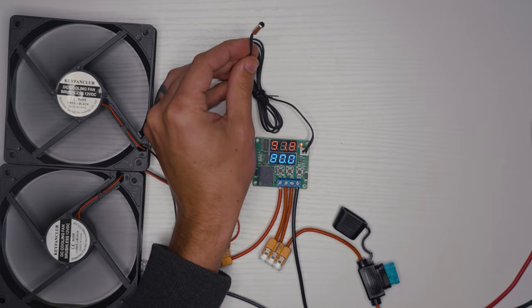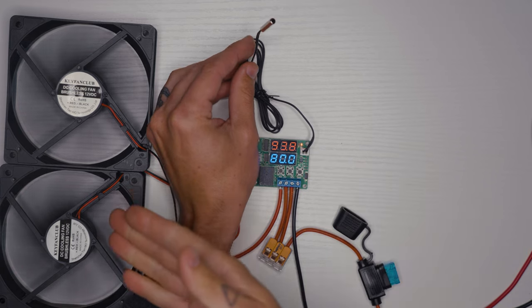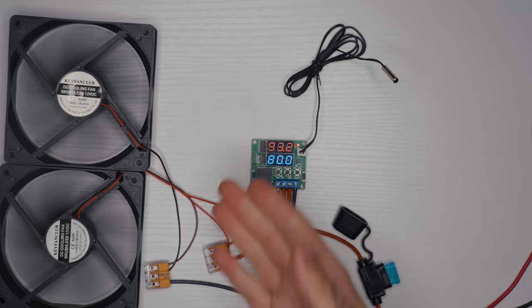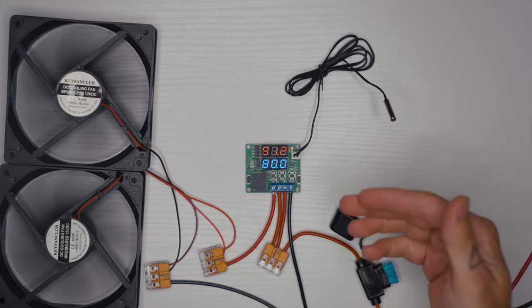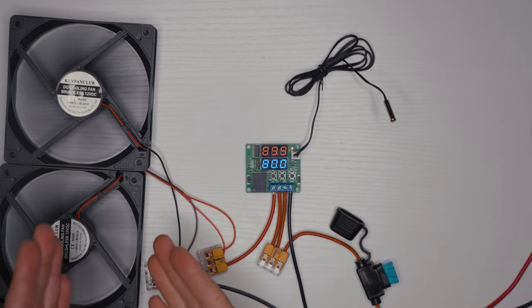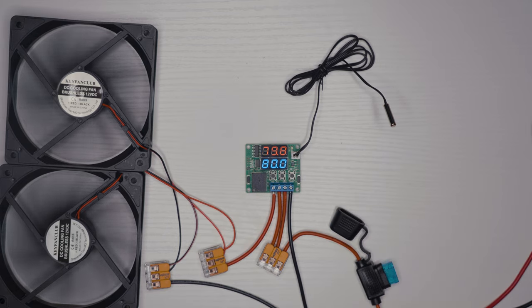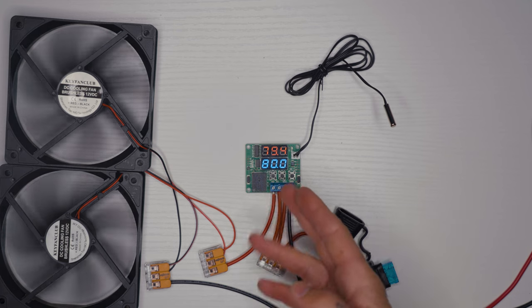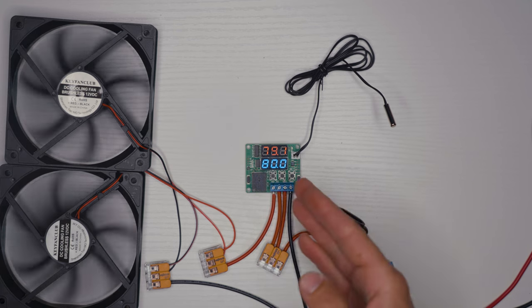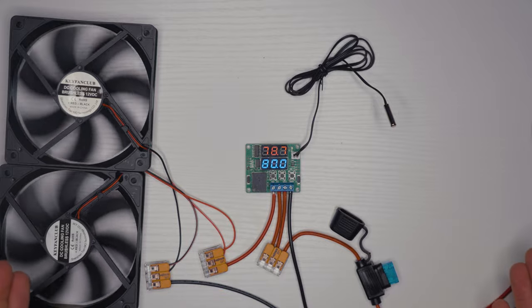So as soon as it crossed over the 80 degree mark, the fans turned on. And now we'll let this cool down to below 80 degrees to make sure that the fans turn off. And we just crossed over the 80 degree mark and the fans turned off exactly how we were wanting it to.